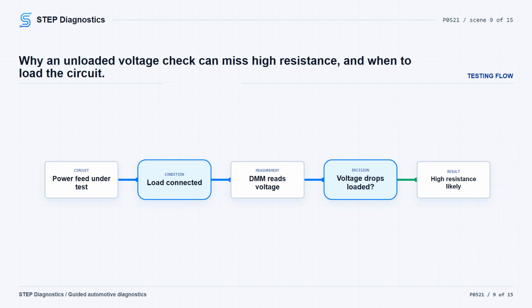For circuits carrying more than 1 ampere, use a load that draws similar current like a brake light bulb. Conductor sizes 20-gauge, 0.8 mm or larger are generally used to carry 1 ampere, 1000 mA or more. A voltage reduction while the circuit is loaded points to excessive resistance. For higher current circuits, voltage drop is the better test.